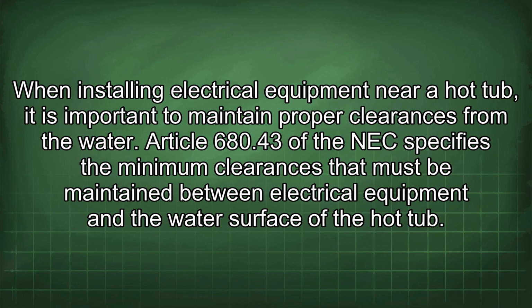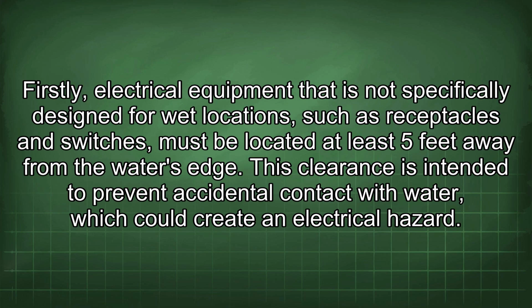When installing electrical equipment near a hot tub, it is important to maintain proper clearances from the water. Article 680.43 of the NEC specifies the minimum clearances that must be maintained between electrical equipment and the water surface of the hot tub. Firstly, electrical equipment that is not specifically designed for wet locations, such as receptacles and switches, must be located at least 5 feet away from the water's edge. This clearance is intended to prevent accidental contact with water, which could create an electrical hazard.